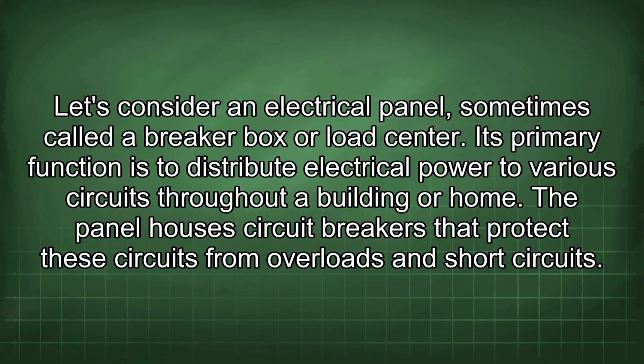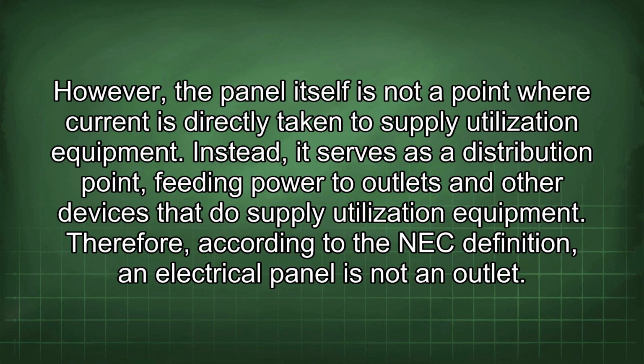Let's consider an electrical panel, sometimes called a breaker box or load center. Its primary function is to distribute electrical power to various circuits throughout a building or home. The panel houses circuit breakers that protect these circuits from overloads and short circuits. However, the panel itself is not a point where current is directly taken to supply utilization equipment. Instead, it serves as a distribution point, feeding power to outlets and other devices that do supply utilization equipment. Therefore, according to the NEC definition, an electrical panel is not an outlet.